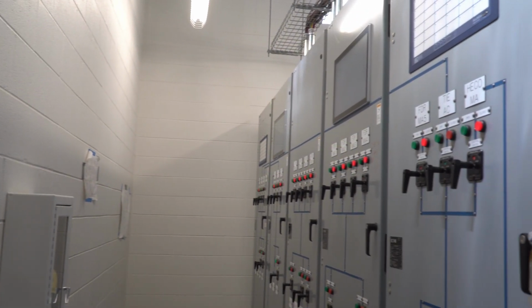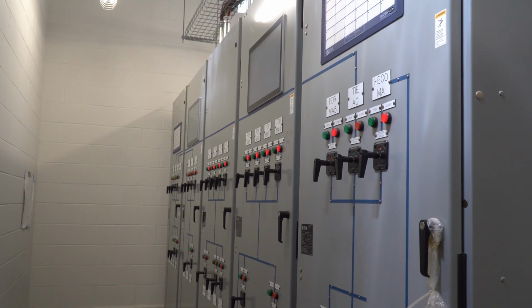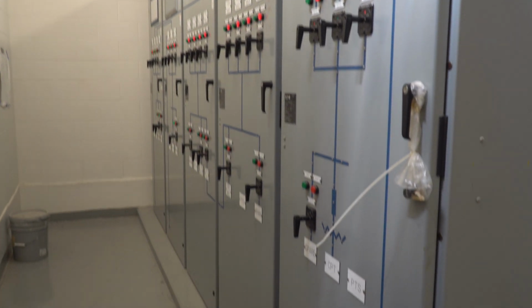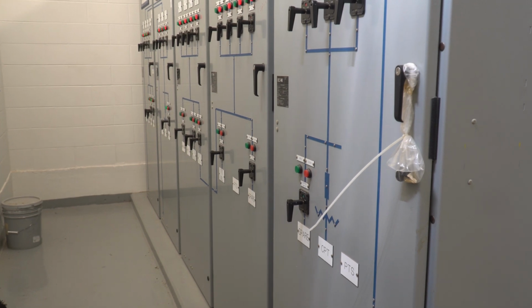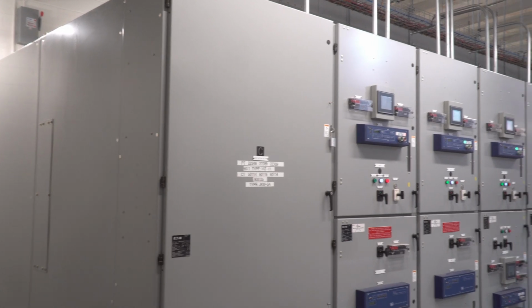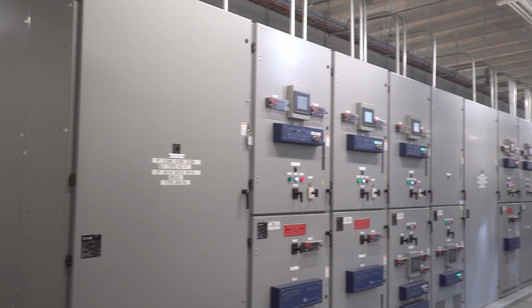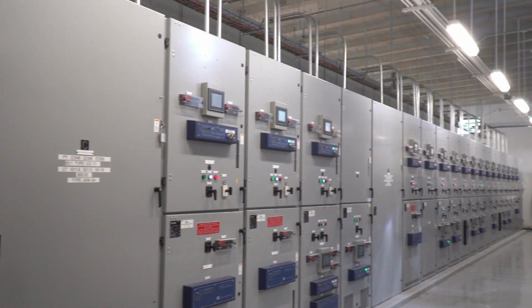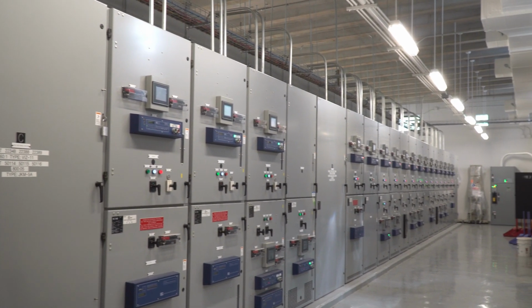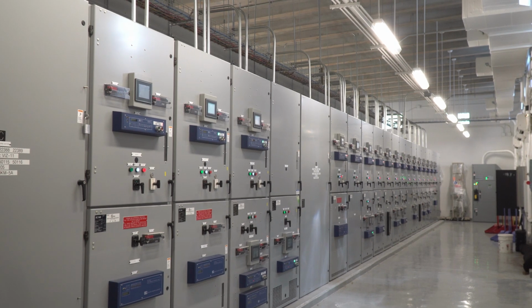Inside each substation, you will find multiple HECO circuits providing the utility power demanded by the campus. These circuits are individually metered. There are 3 utility meters feeding Substation M and 3 for Substation L. Each of these meters can run most of campus, making the campus energy supply dual-triple redundant.